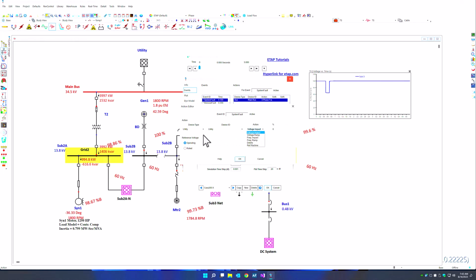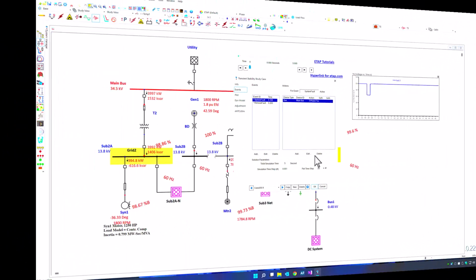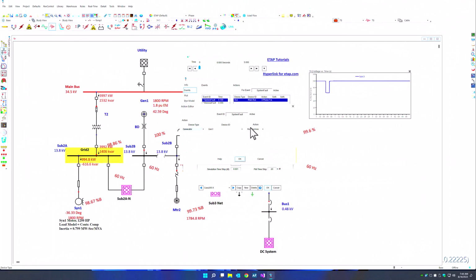In ETAP 22, you can also go to the utility and select between voltage impact ramp and frequency impact ramp. And these options essentially allow you to simulate the impact of high voltage ride through or low voltage ride through, including frequency ride through capabilities by changing the behavior of the power grid and observing the response of the rest of the system with respect to the change in these actions. You can also go to the generator and select from new options, including generator impact, ramp, and voltage impact and ramp for synchronous machines as well.